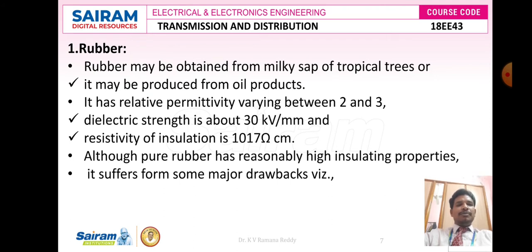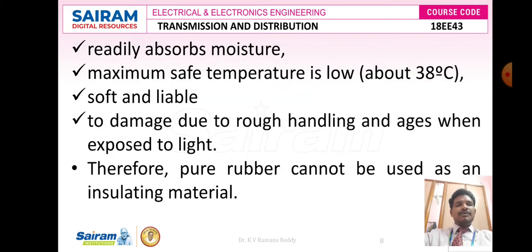The first insulating material is rubber. Rubber may be obtained from the milky sap of tropical trees or it may be produced from oil products. It has a relative permittivity εr which varies between 2 and 3, a dielectric strength of about 30 kV/mm, and resistivity of insulation ρ around 10¹⁷ ohms per centimeter. Although pure rubber has reasonably high insulating properties, it readily absorbs moisture from the atmosphere and soil. Its maximum safe temperature is low — it can withstand a maximum of 38°C — and it is soft and liable to damage due to rough handling and exposure to light. Therefore, pure rubber cannot be used as a direct insulating material.